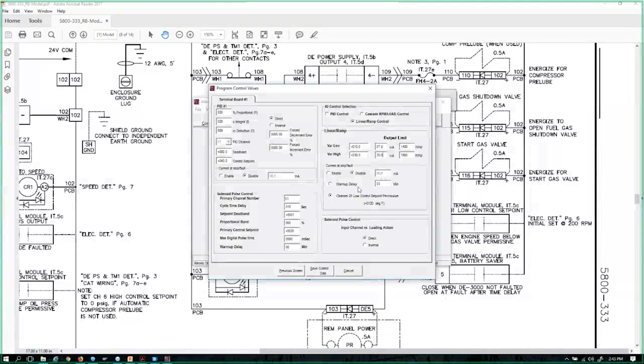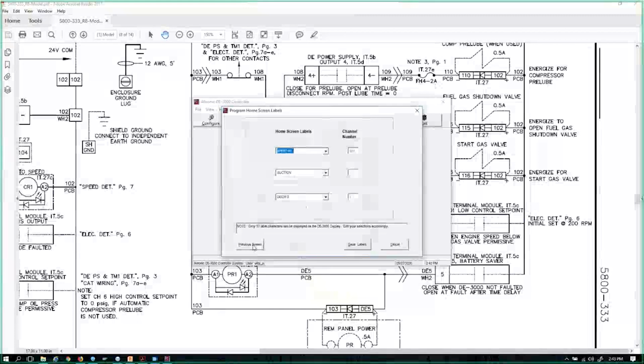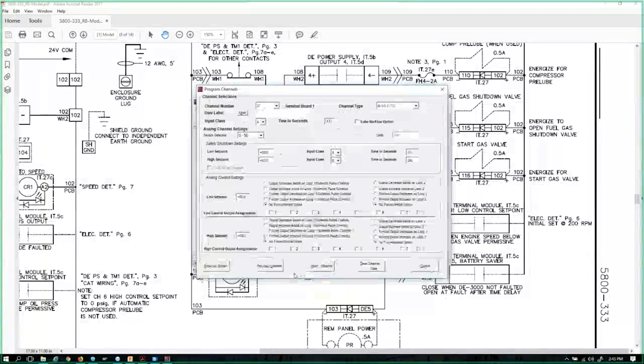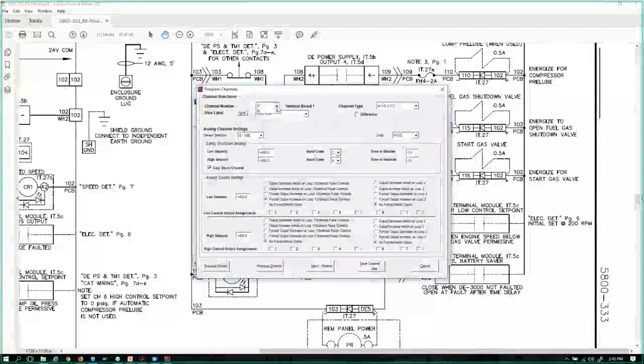Warm-up delay. We can do warm-up 2 different ways for this circuit to start working. We can put a timer in here, or we can link it to channel 26 low control set point permissive, currently set at 120 degrees. Some of you may be asking, well, wait, what's channel 26? So let's go take a look. I'm going to save, and then I'm going to back up, and use this drop-down arrow because it's quicker, to channel 26, and we can see that channel 26 is compressor oil temperature. It's a 0 to 5 volt or thermocouple. It's configured as a thermocouple, and it's set to the low control set point.